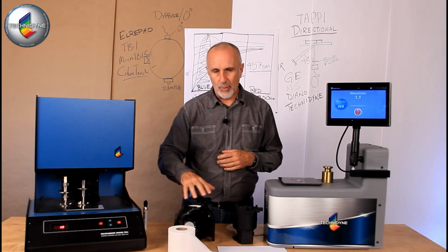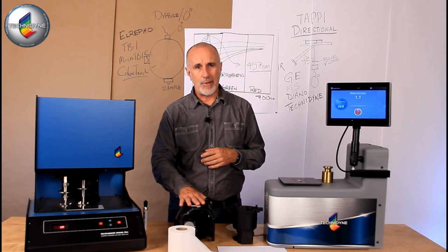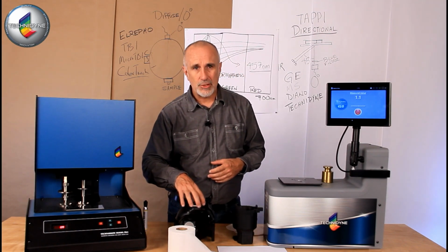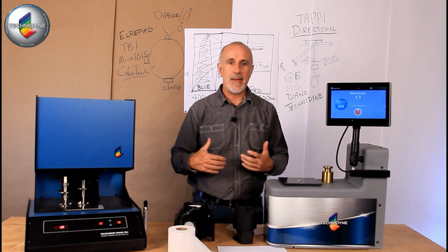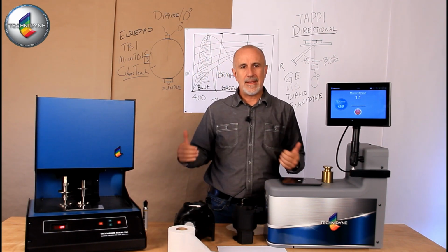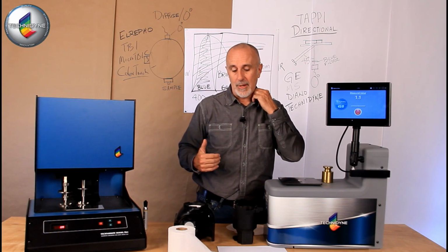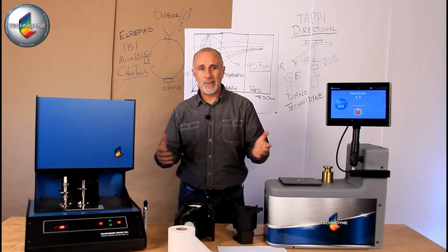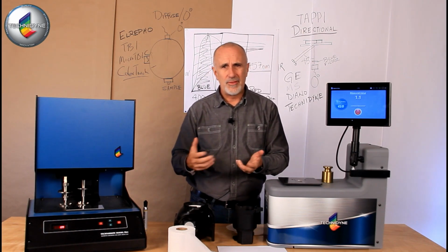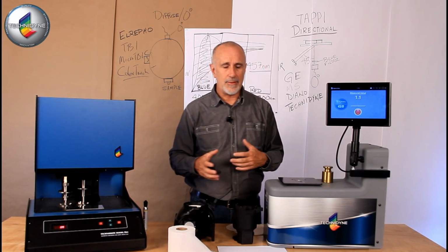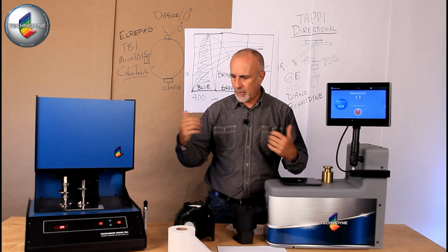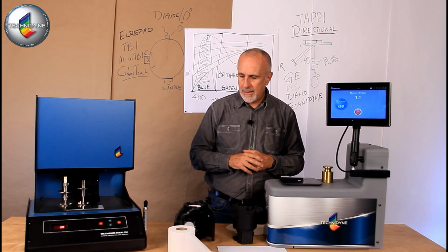So the ISO group, after a couple of years of having this in the marketplace, realized that was an error. So they put this black gloss trap insert in here, and so now today we make all the ISO instruments with that gloss insert in there so that we take out as much of the effective gloss as we possibly can. But the two products, because of the geometric difference, do handle the effect of gloss differently between one to the other. So you've got the geometric difference, you've got the photometric difference, which we'll talk about in calibration.